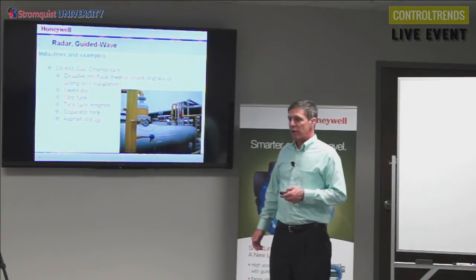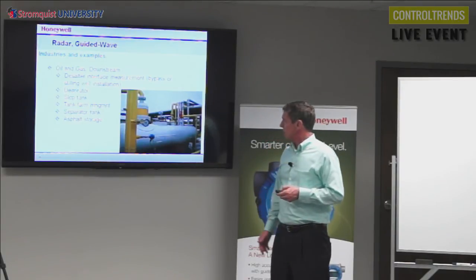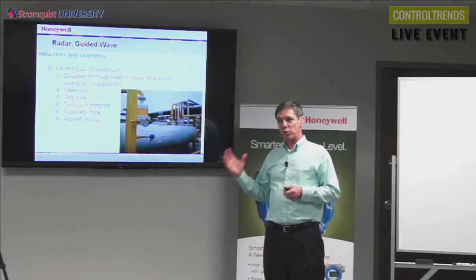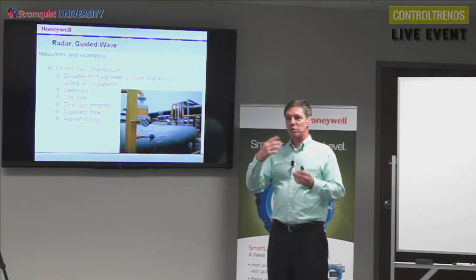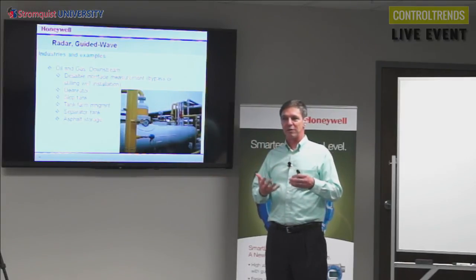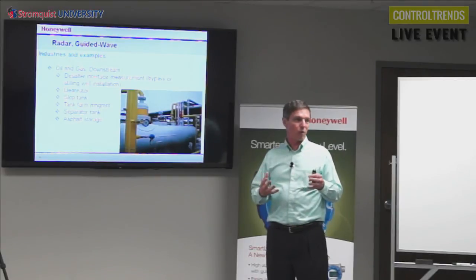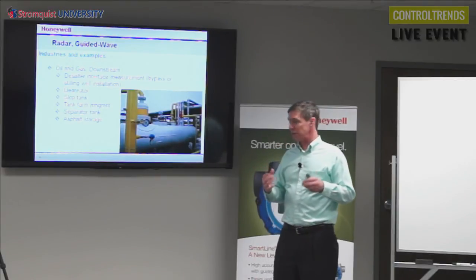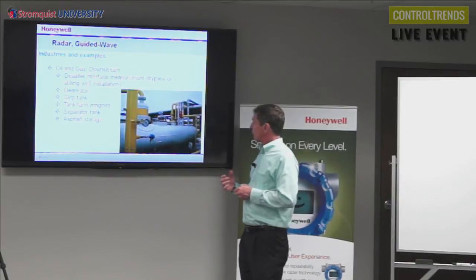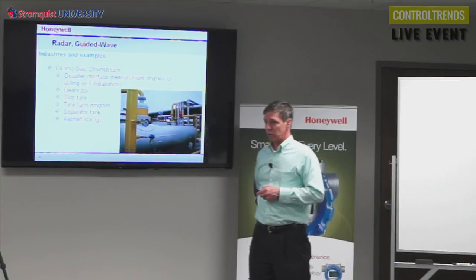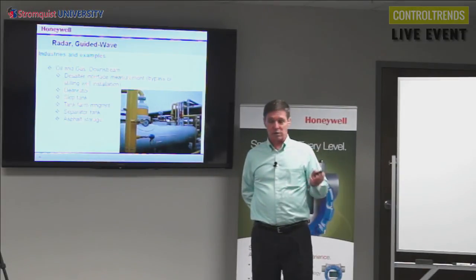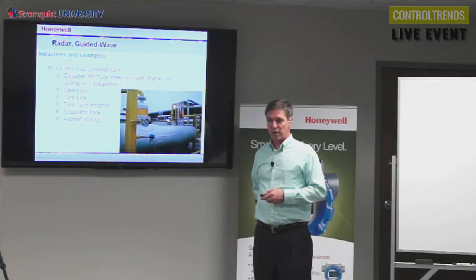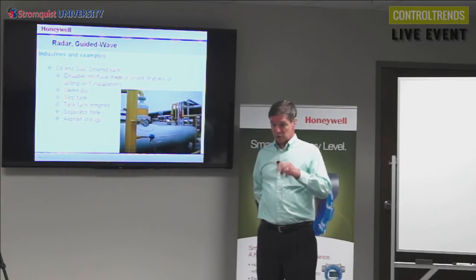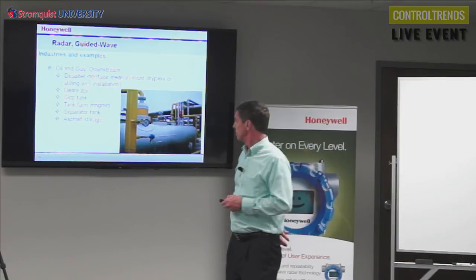Continuing with refineries, the desalter is really the first stage as the crude oil comes into the refinery. So it's got some sand in it, some water, some oil, and there's a little bit of separation that still needs to happen. And the desalter can be kind of a challenging application, but it's good for guided wave because the density is kind of variable. It's not well known, but there can be some concern with emulsification there.